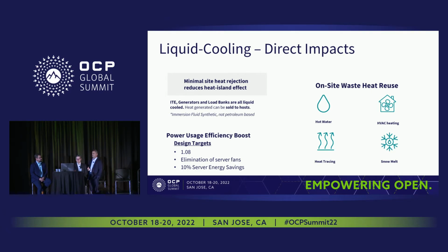We've also eliminated the server fans in the scenario where a tenant decides to deploy immersion. We can support any of the three ACS solutions, but if we see immersion across the board in the data halls, the typical parasitic power draw from server cooling fans in an air-cooled deployment can average anywhere from about 10% to 15% of total server power draw. So a 30 megawatt data center running single phase immersion is actually using all 30 megawatts worth of UPS capacity to perform compute, network, and storage.